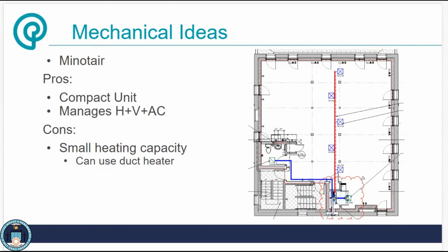And when it's in recirculation mode, it'll provide standard heating and cooling for a space, as well as dehumidification. They're a little smaller in capacity. They're only about a ton, and they have a slightly smaller heating size, but you can boost that with either an electric resistance duct heater, or there's a hydronic one as well if you've got a DHW system that you want to feed hot water to that coil.